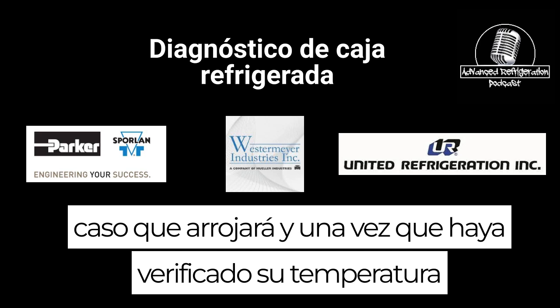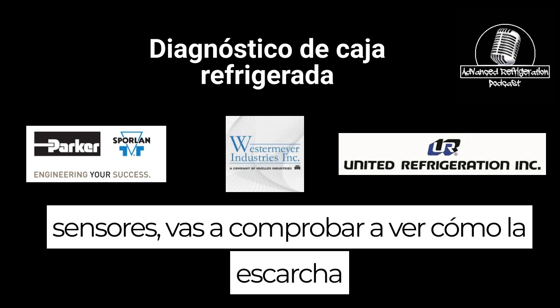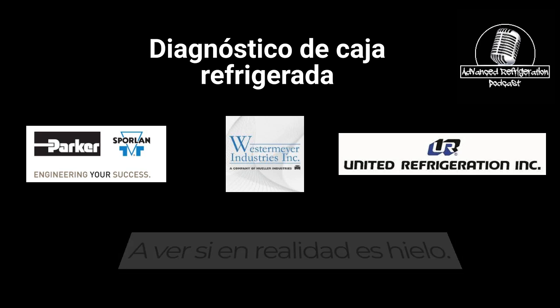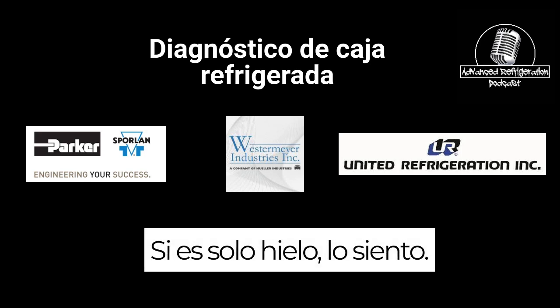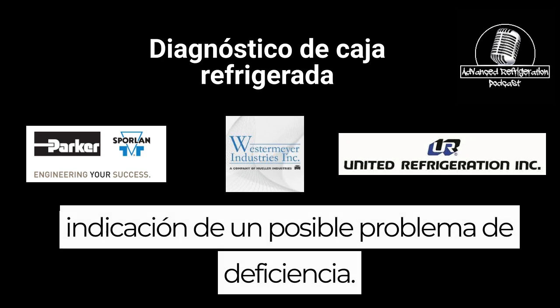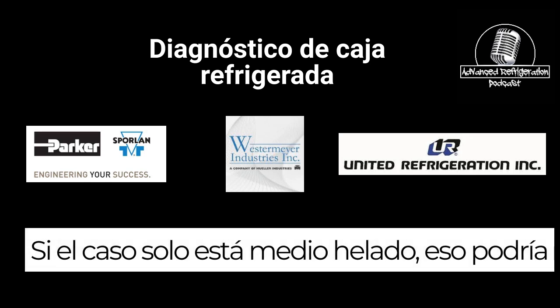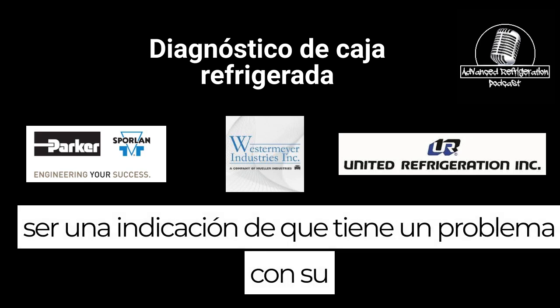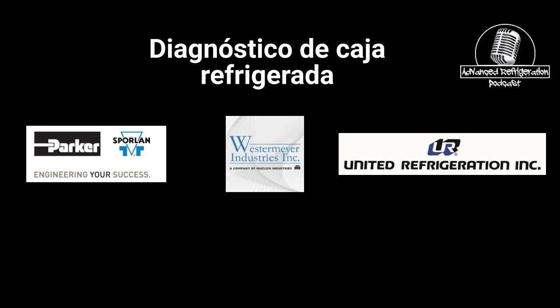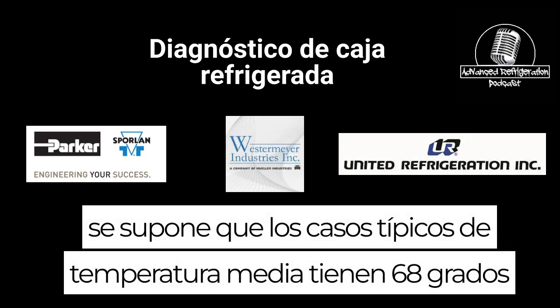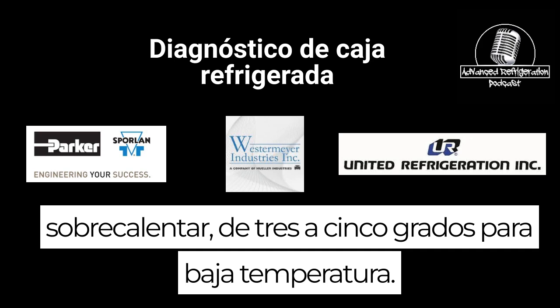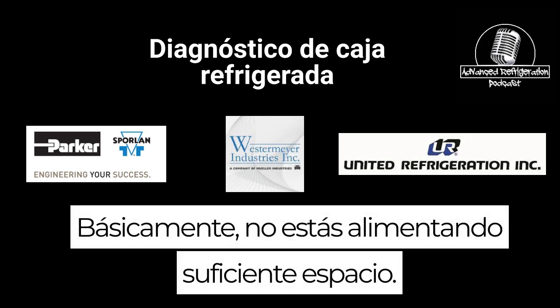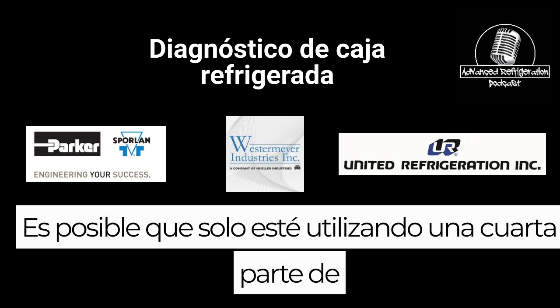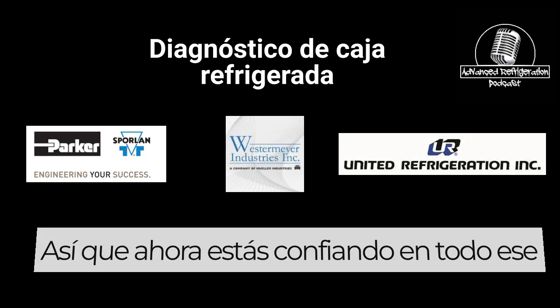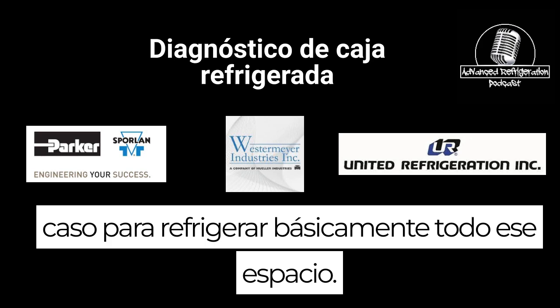And once you've verified your temperature sensors, you're going to check to see how the frost pattern is on the case. See if it's actually iced. If it's just iced, that might be an indication of possibly a defrost issue. If the case is only maybe halfway frosted up, that might be an indication that you have an issue with your superheat. Your typical medium temp cases are supposed to have 6 to 8 degrees superheat, 3 to 5 degrees for low temp. If your superheat is off, think about it. You're not basically feeding enough refrigerant. You might only be utilizing a quarter of the coil, a half of the coil. And so now you're relying on that whole case to basically refrigerate that whole space.